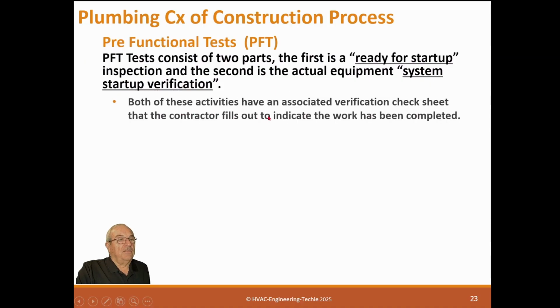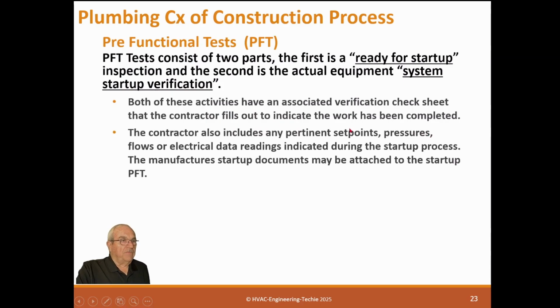Both of these activities have an associated verification check sheet that the contractor fills out to indicate the work has been completed. The contractor also includes any pertinent set point, pressure, flow, or electrical data readings indicated during the startup process. The manufacturer's startup documents may be attached to the startup PFT, because a lot of times the contractors are obligated to do the manufacturer's equipment startup, because that's part of their warranty process.